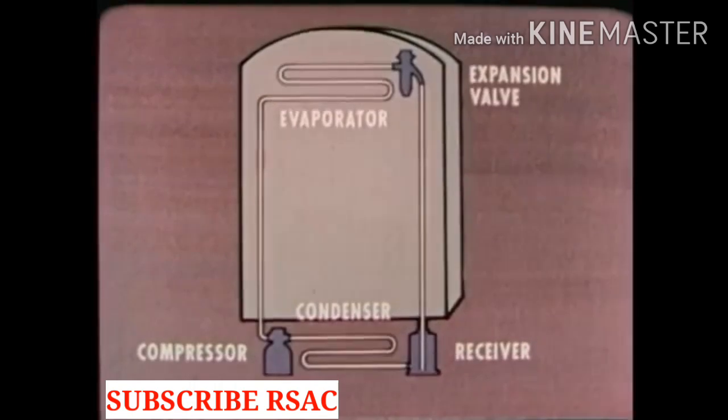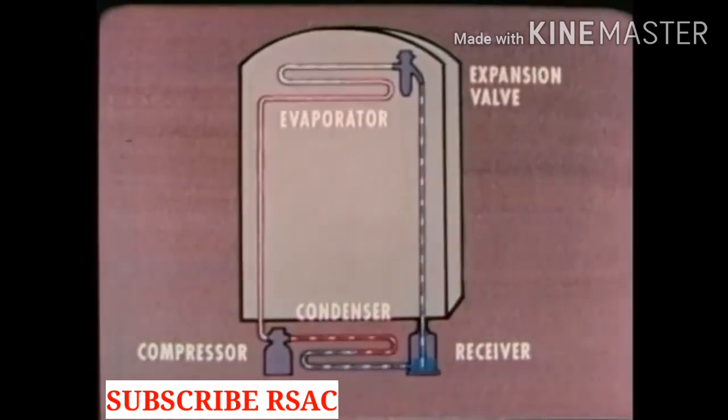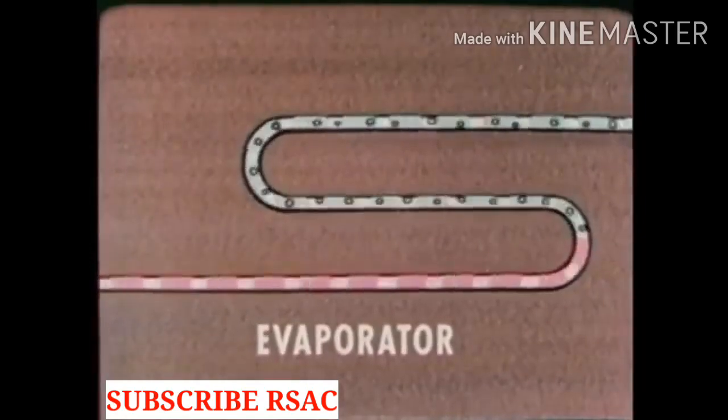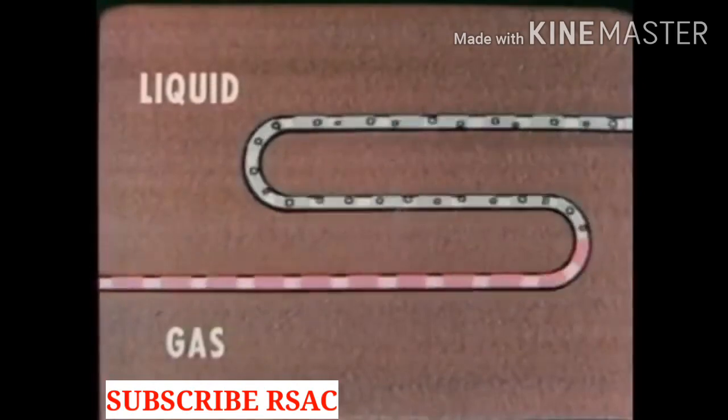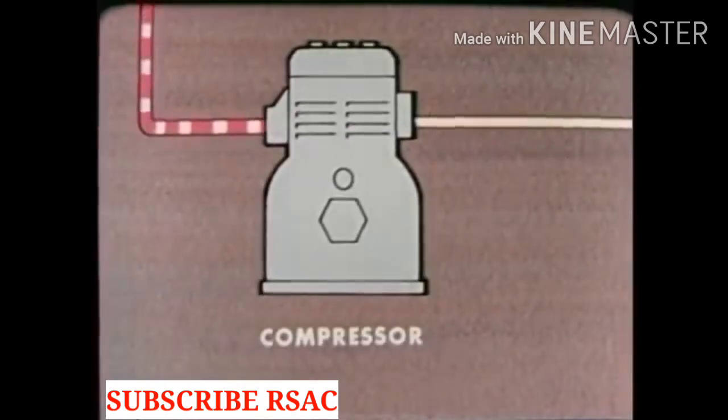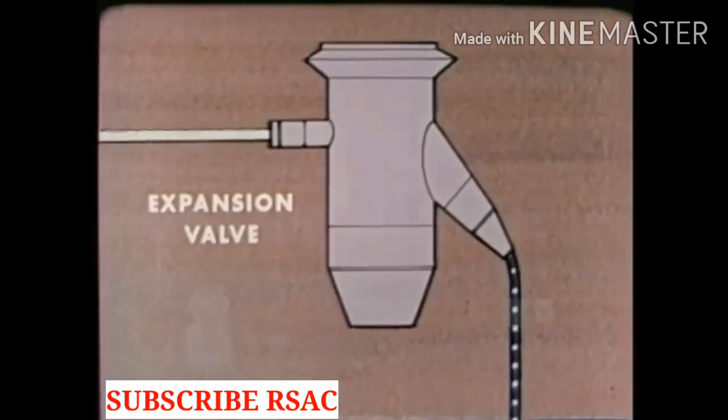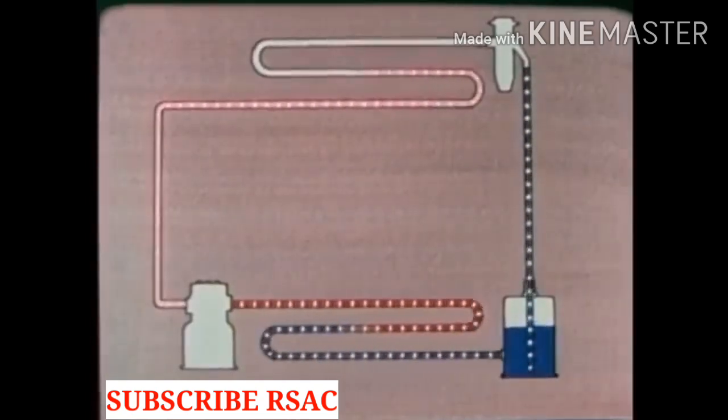Also in the system are the compressor, which is a pump, the expansion valve, and in many systems the receiver, a kind of storage tank. A chemical substance called the refrigerant flows through the system. It's the refrigerant that picks up BTUs of heat from inside the box and discards them outside. In the process the refrigerant changes from a liquid to a gas, then in the condenser it changes back to a liquid. At the same time the pressure increases in the compressor and decreases in the expansion valve. Before you can understand how the system works you must learn why and how these changes take place. That means learning some basic principles concerning heat.